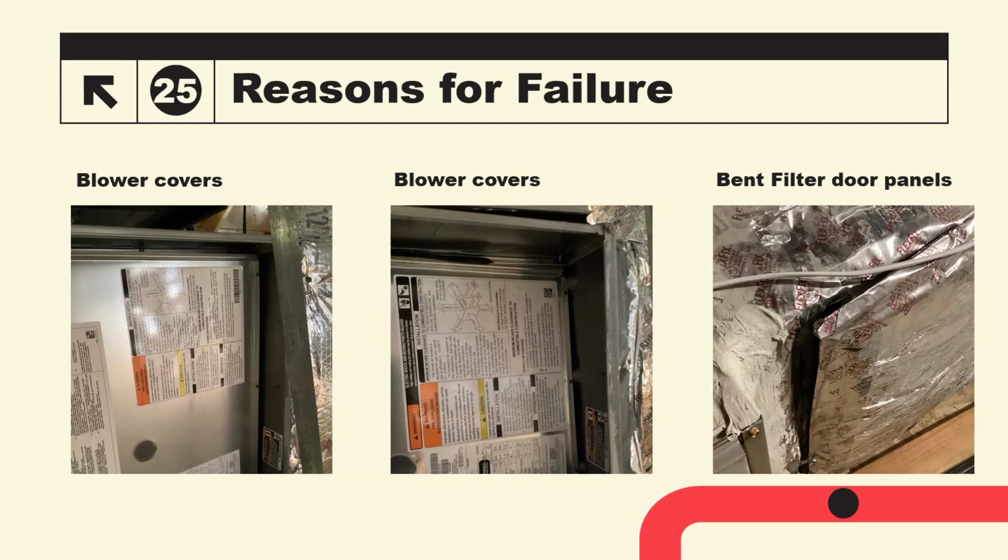Again, a third party is not allowed to tape all that stuff up. It needs to be properly sealed and installed as it should be from the manufacturer. I know it's not the HVAC contractor's fault. It's the electrician's fault. But 9 times out of 10, the electrician will not be the one coming back to fix that. It's going to be the HVAC contractor that has to come back and do it.